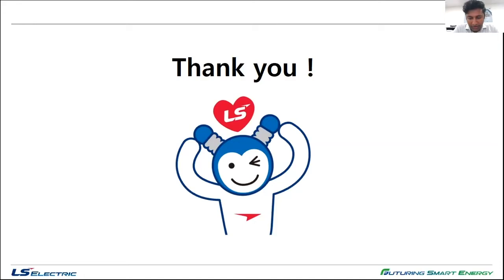But in our same specification, we have an option where you want to precisely use the neutral input. Then there is a trip unit function, which is AN type, I believe. I can let you know the exact type. There is an additional trip unit where you can get the neutral CT input also. But in the AG5 trip unit, there is no provision to get the neutral input. So it works on the current imbalance principle.